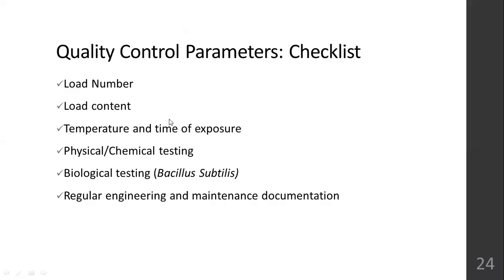Okay. For each cycle of sterilized instruments, do they mention these things on the sterilization label? The load number, whatever was inside the load, temperature at which it was operating, time of exposure, and chemical testing and physical testing we'll see now. That's when you will understand. The results of it should be there on the load.